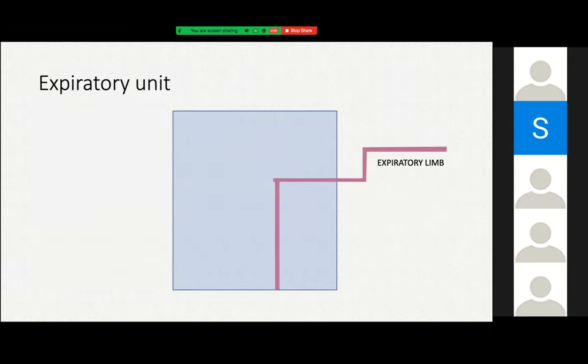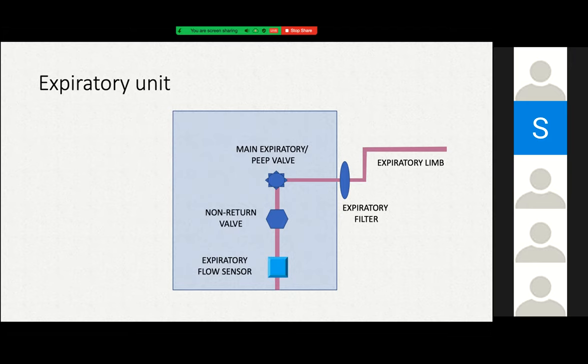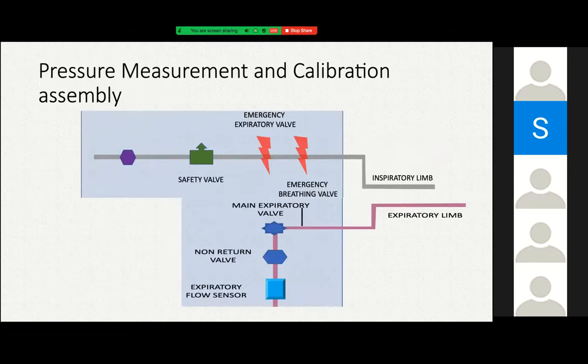The expiratory limb typically has an air filter before the exhaled gases enter — they are filtered mainly for bacterial content. We also have a PEEP valve, which is a solenoid valve, and this is where PEEP is regulated. There is also a non-return valve to maintain unidirectional flow and a flow sensor. Together, these make up the hardware of the ventilator.